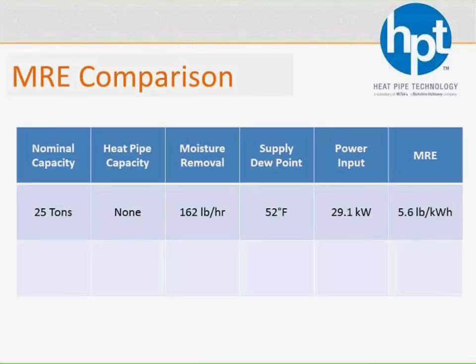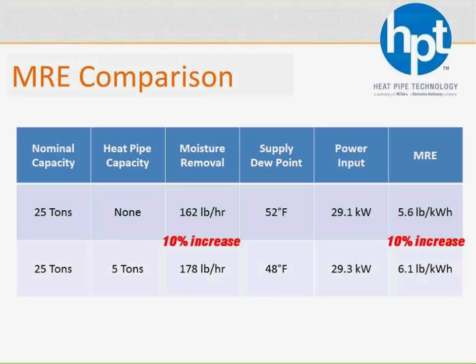So let's take a look at that same example, but now instead of downsizing the equipment to get the same capacity, we're going to use the same equipment, add a heat pipe to it, so now that coil is able to do more latent cooling and remove even more moisture, dropping that dew point from 52 all the way down to 48 degrees, and it's done so at such little power because, again, all we're doing is adding a little bit of static pressure, so a little bit more brake horsepower for the fan to overcome. And now we've removed about 10% more moisture and improved the MRE by 10%. So you can either downsize the equipment to make it way more efficient, or you can keep the equipment the same size, dry out the air further, and still make it more efficient, which is pretty awesome.